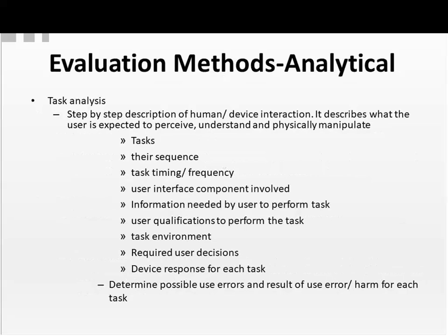So let's go through some analytical evaluation methods. Task analysis is a step-by-step description of the human-device interaction. Describes what the user is expected to perceive, understand, and physically manipulate. It's a detailed evaluation of each task.